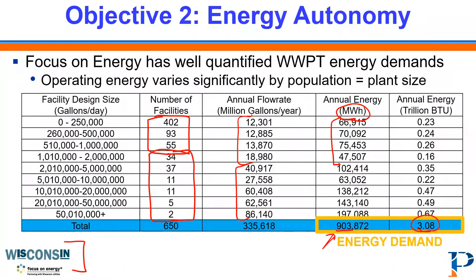Now, it's been pointed out that of the 88 large wastewater treatment plants in the state, they've got a total energy generating potential of about 50 megawatt nameplate capacity. They treat about half of the water in the state, but if we look at the total nameplate capacity of 50 megawatts between these intermediate and larger size plants, their annual energy production is something of the order of 438,000 megawatt hours of energy, or 1.5 trillion BTUs. And as we saw, that's about half of the energy demand for operating wastewater treatment centers statewide.